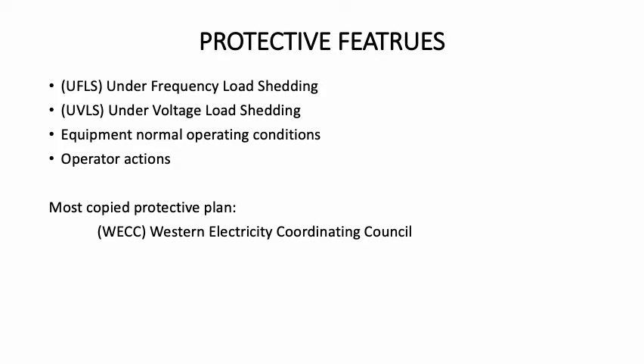Load shedding means removing portions of the load in hopes to bring back balance to the demand and generation differences. They begin with non-vital loads to hopefully prevent further losses and to affect fewer people. The equipment itself has built-in protective features and also normal operating conditions that are designed to prevent damage or loss of equipment.